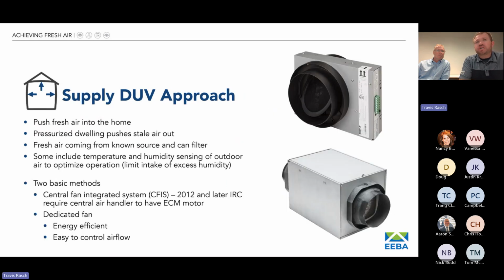The next approach is that supply. So this is where we have a dedicated duct that runs from the outside to the inside of the home, passing through this type of product. So we have a known source of air, fresh air. In most cases, we're going to filter it, whether it's with a damper going through your return side filter, or in the case of a supply fan where there's dedicated filtration within the product itself. So again, a known source of fresh air. We're going to positively pressurize that envelope by using this supply strategy.